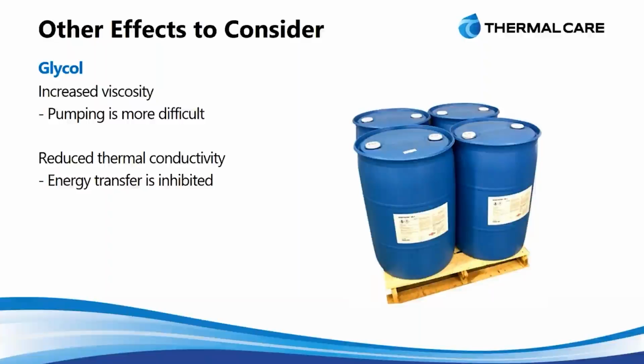Additionally, the glycol being mixed in there actually reduces the ability of that process fluid to absorb energy. It acts almost like an insulator. So it inhibits that energy transfer, which is the whole point of a chiller. And again, that's affected by the percentage of the glycol that's in the water. So those are things to be cognizant of when evaluating your system's requirements for a chiller.